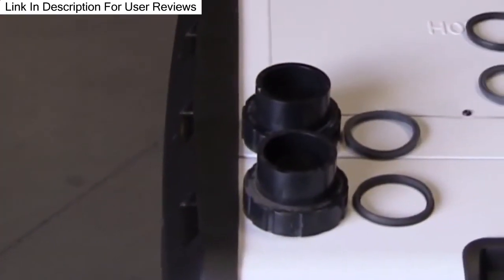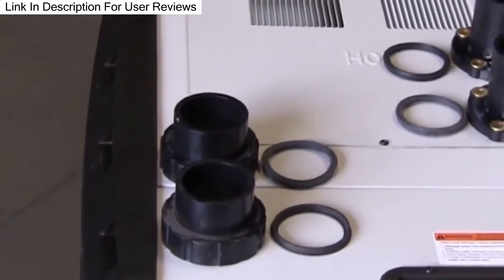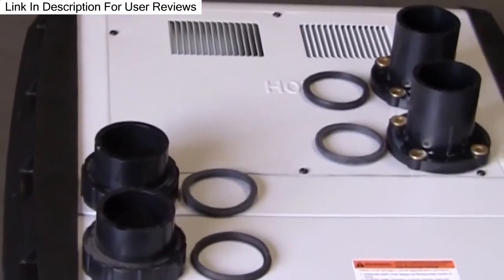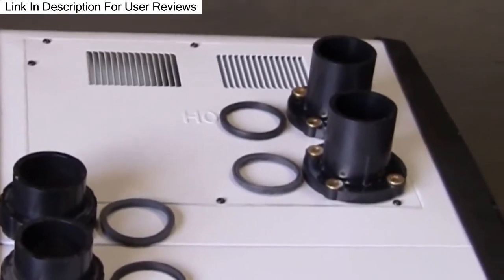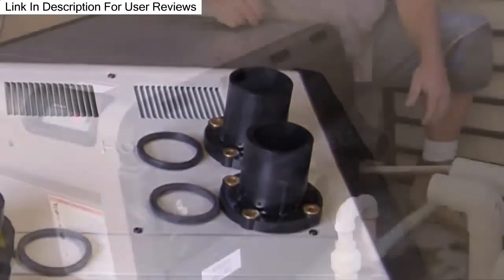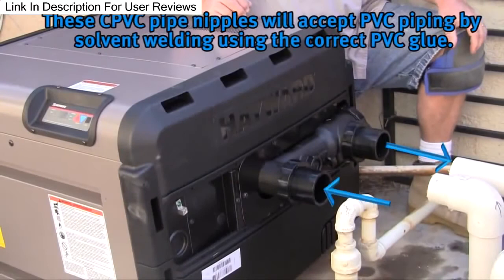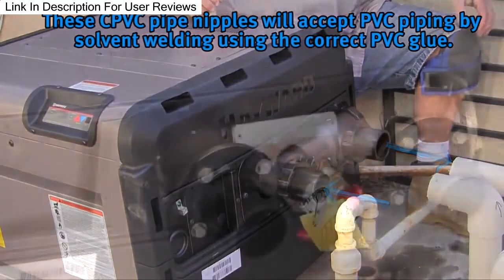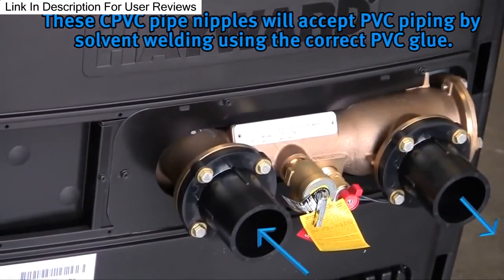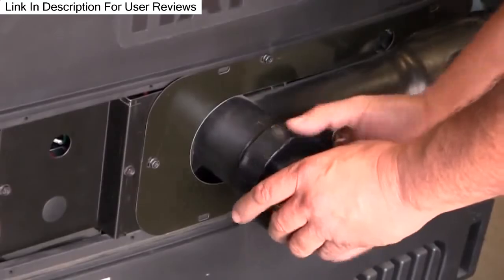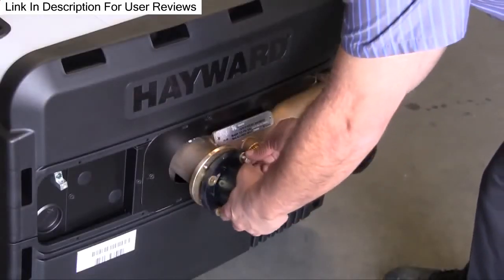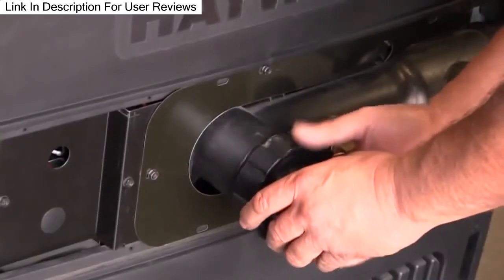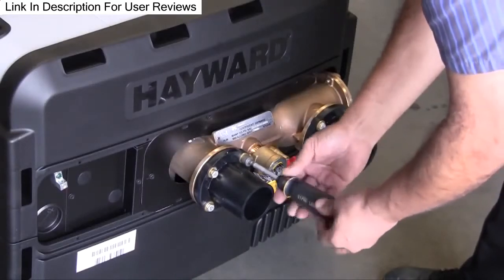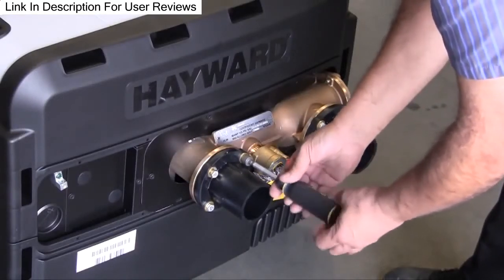The residential heater model is equipped with a CPVC union kit, while a CPVC flange nipple is bolt connected to the commercial heater model. These are used to accommodate water piping to and from the pool or spa. These pipe nipples will accept PVC piping by solvent welding using the correct PVC glue. Assemble the union kit or flange nipple to the heater prior to plumbing. Tighten union nuts or bolts securely before gluing fittings or pipe to the nipples or flange.